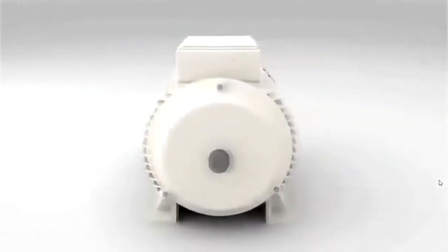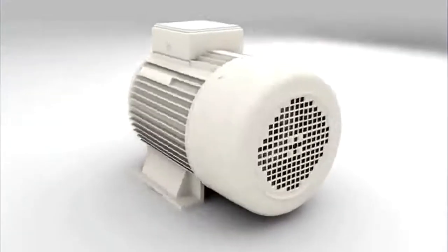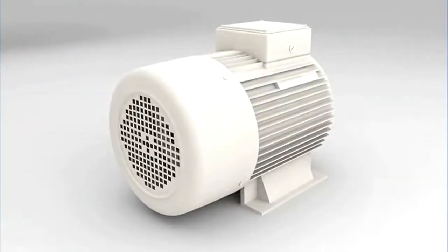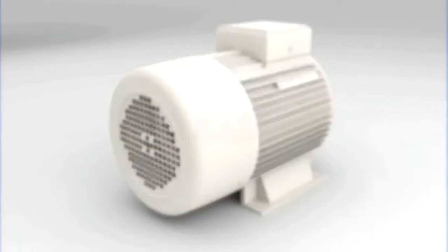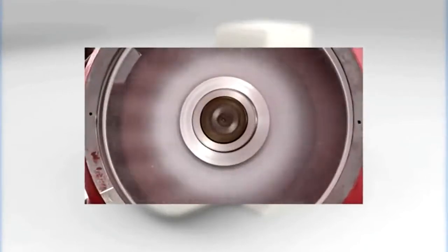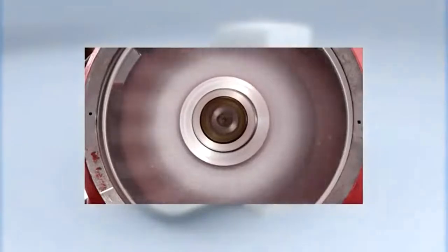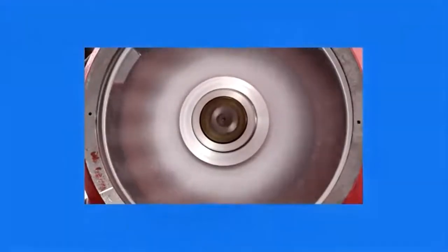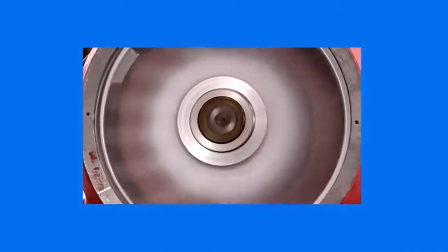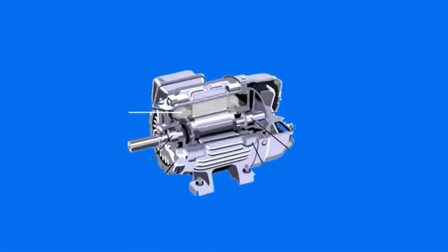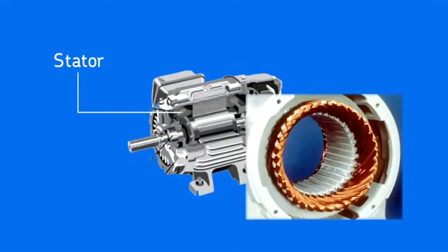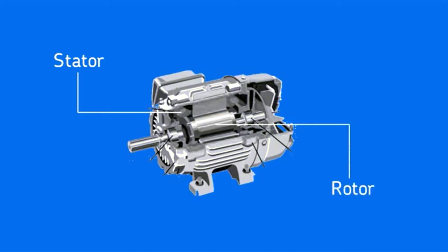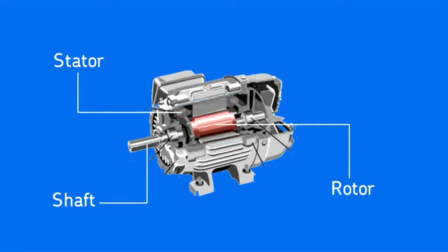AC induction motors make up the majority of industrial electric motors. Industrial AC induction motors use magnetic fields to cause the shaft rotation. Magnetic fields are created by electric currents. The AC power source provides the currents that flow in the motor. The stationary part of the motor, the stator, is made of several wire loops which are physically aligned to create strong magnetic fields. Due to the AC nature of the power source, the magnetic field direction rotates in the center of the stator. In the center of the stator is the rotor, the part of the motor which is connected to the shaft and rotates. The rotor has no electrical connections to the stator or the power source. Rather, the magnetic fields of the stator induce currents to flow in the rotor. These rotor currents create a magnetic field which interacts with the stator magnetic field to create the shaft rotation.